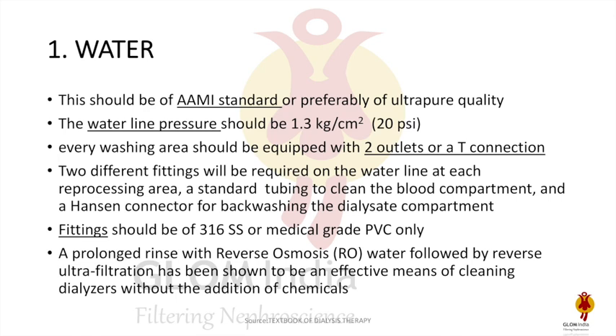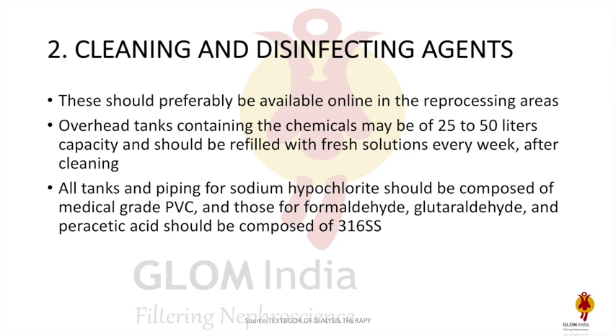For fittings, generally 316 stainless steel or medical-grade PVC is used. Very importantly, prolonged rinse with RO water followed by reverse ultrafiltration has been shown to be an effective means of cleaning the dialyzer without the addition of chemicals. The second requirement is a cleaning and disinfecting agent.